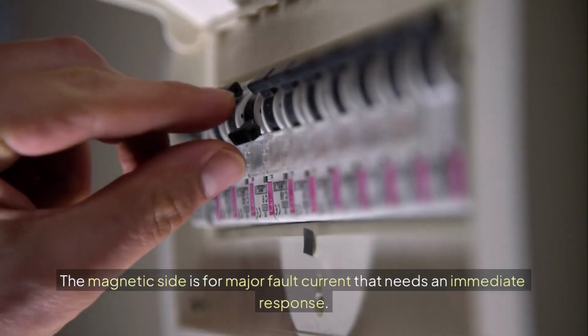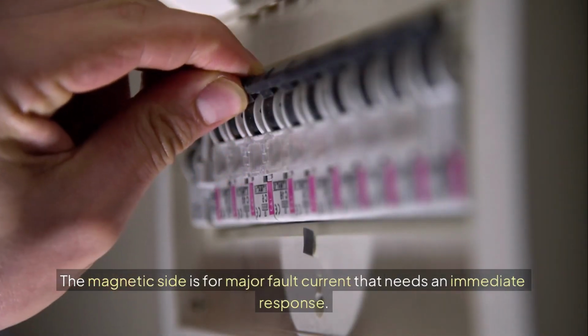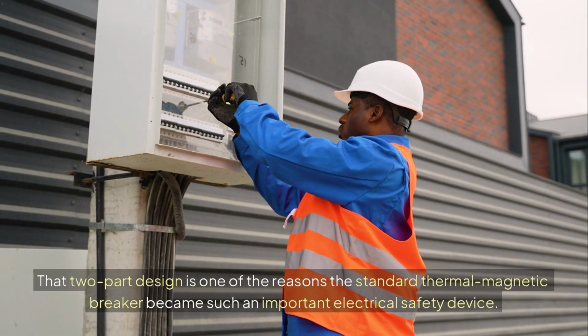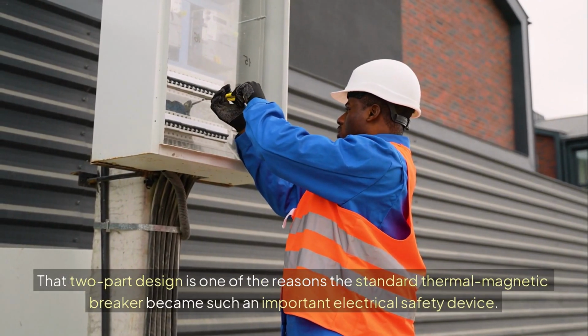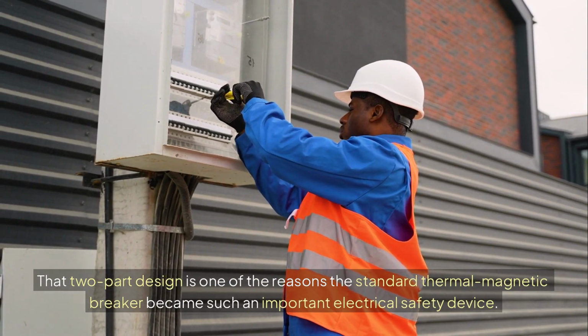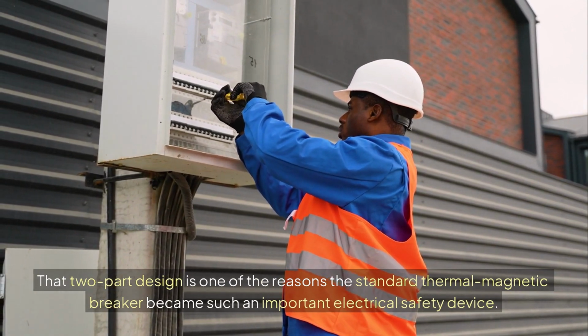The magnetic side is for major fault current that needs an immediate response. That two-part design is one of the reasons the standard thermal-magnetic breaker became such an important electrical safety device.